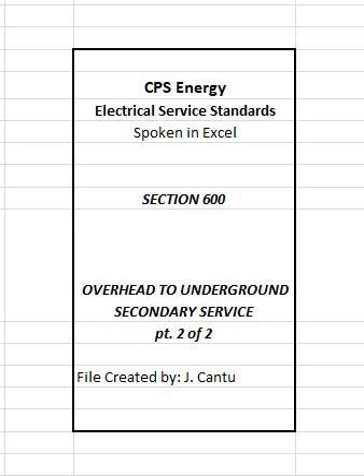D. Junction/pull box. Directly to customer's service entrance conductors within junction box which is required by CPS Energy ahead of an auxiliary wire gutter. The junction box shall be sized and installed in accordance with Figure 802 and shall be provided with lockable and sealable means for use by CPS Energy due to unmetered conductors. Junction box and auxiliary gutter shall be furnished and installed by customer. Exception: junction box is not required ahead of auxiliary wire gutters serving duplex installations where gutters have minimum dimensions of 16 inches H x 8 inches D x appropriate length required to extend under each meter socket.